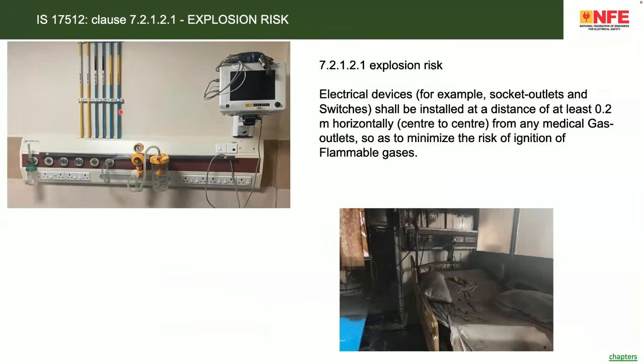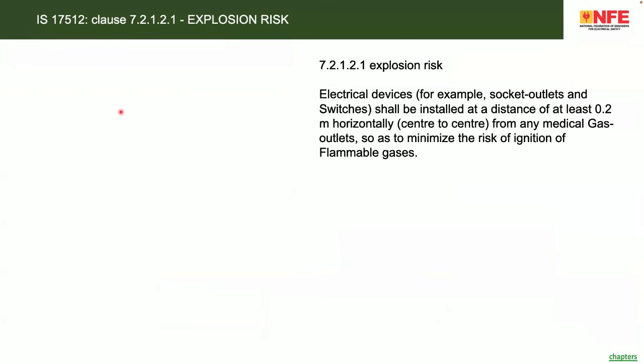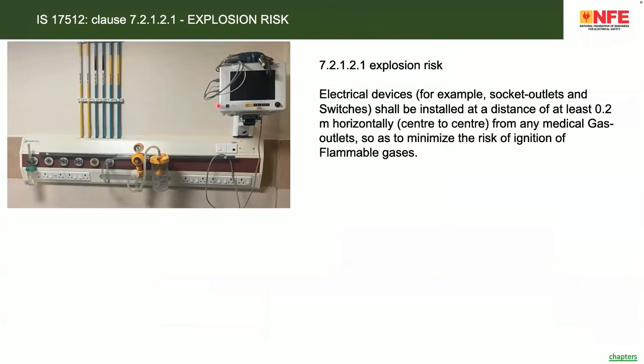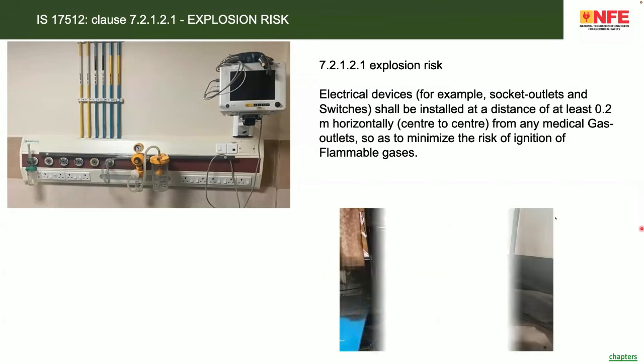I was just reading from the standard, clause number 7.2.2.1, explosion risk. Electrical devices, for example socket outlets and switches, shall be installed at a distance of at least 0.2 meter horizontally from any medical gas outlet so as to minimize the risk of ignition of flammable gas. Now on the left side, you can see a picture. There is a medical gas supply as well as the electrical supply in the same arrangement, and you can see the distance. This kind of installation is very common in India. Probably in 50-60% of the hospitals you can find this kind of installation. The requirement is that medical gas should be at least 200 millimeters away from electrical sockets. You are not supposed to make it in this way.